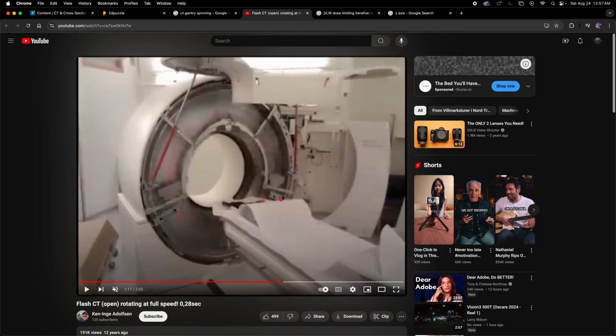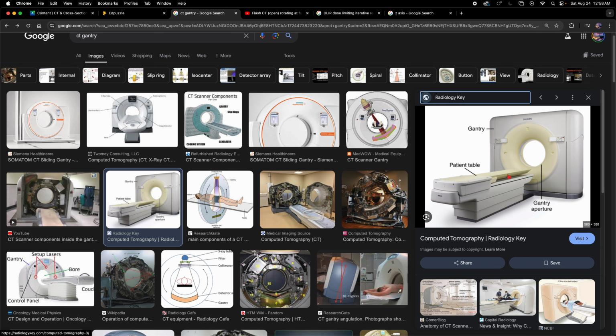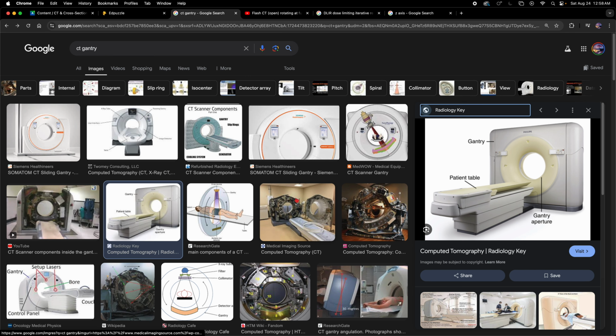And so it stands to reason that if for X-rays you use a short exposure time to limit the impact of motion artifact, it's the same thing for CT. So you have a patient who is restless, or they have trouble remaining still, you might want to speed the gantry up. And that's similar to the reasons why we use a shorter time in X-ray. So you just speed the gantry up in CT to get a shorter examination time. What would that do? That would make the table move faster in and out of the gantry. We get a quicker examination, and it lowers the impact of motion artifact.